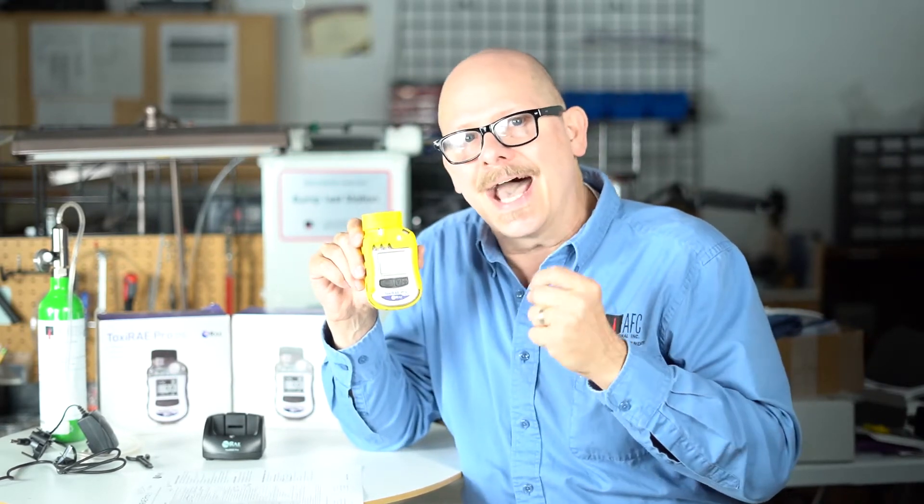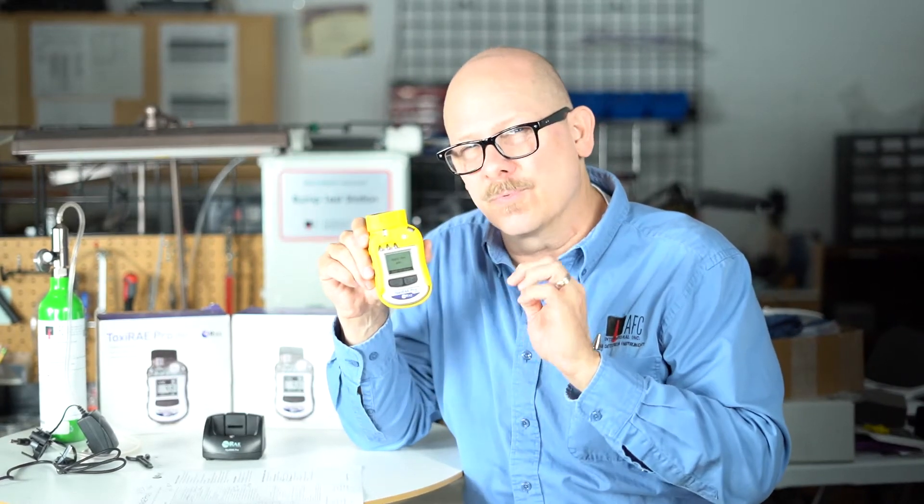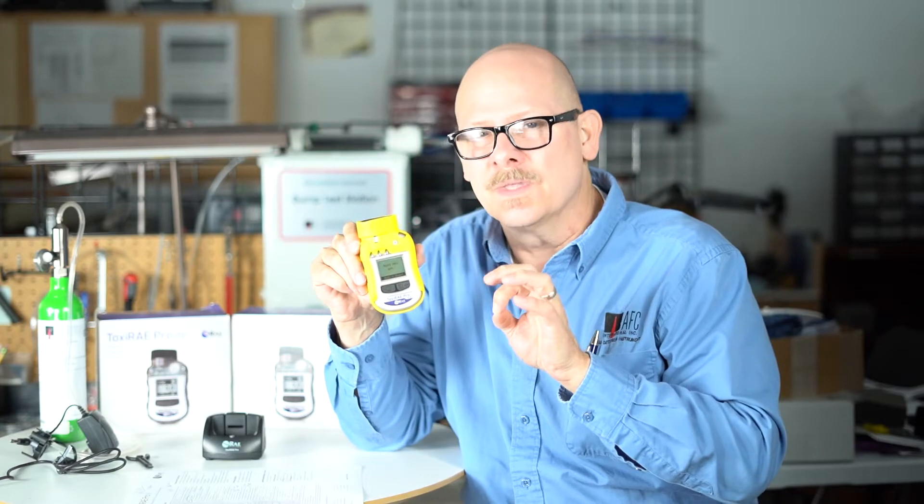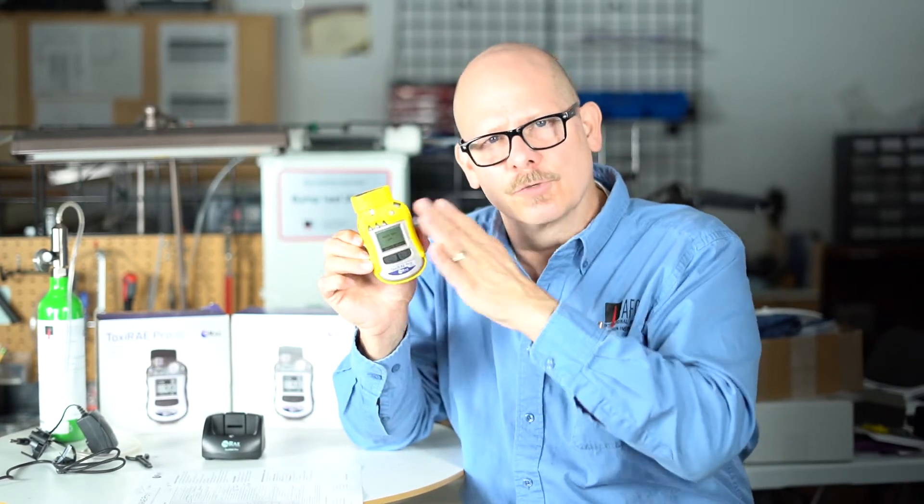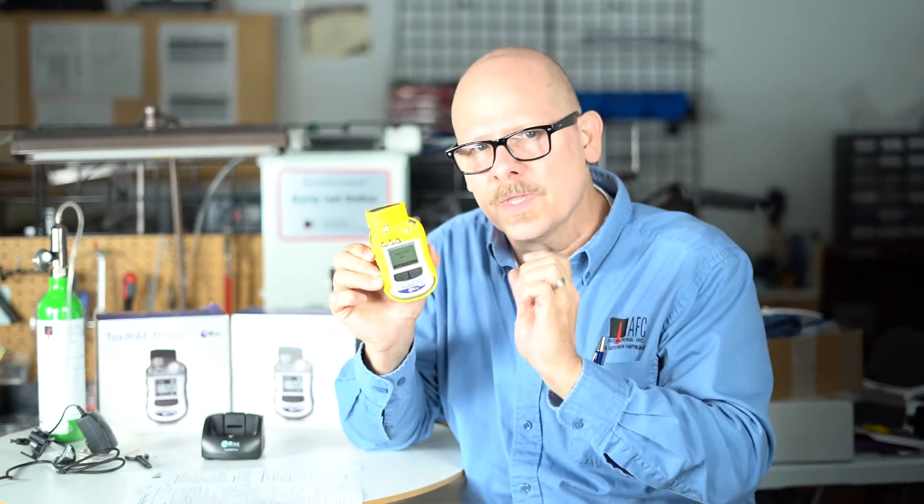I was just at a plant, and we were detecting for acrolein. Acrylin has an IDLH level of two parts per million. The time-weighted average is right around 0.2 to 0.3. So in those cases, I would have to go with the industrial hygiene version to get down to that low level.